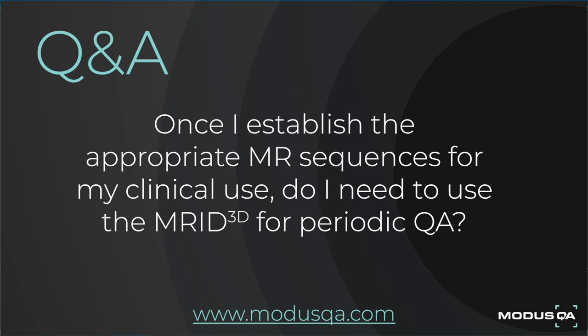Once I establish the appropriate MR sequences for my clinical use, do I need to use the MRID 3D for periodic QA? Yes, this is a great question. Different sites have different philosophies and approaches. The task group and consortium recommendations note that gradient nonlinearity typically does not change much over time unless you have an upgrade from your vendor. B0 distortion, though, can be more variable in time. So some sites will do a B0 measurement on a daily basis, whereas they will do a more intense scan for more information on a periodic basis, perhaps monthly or every two weeks.